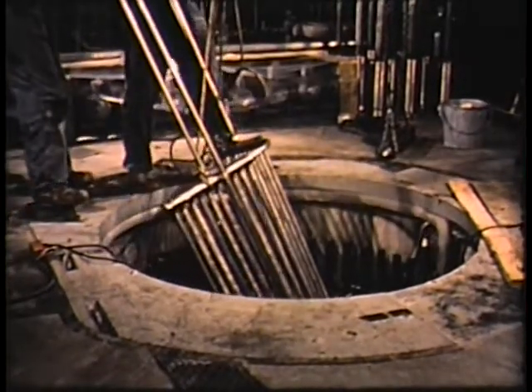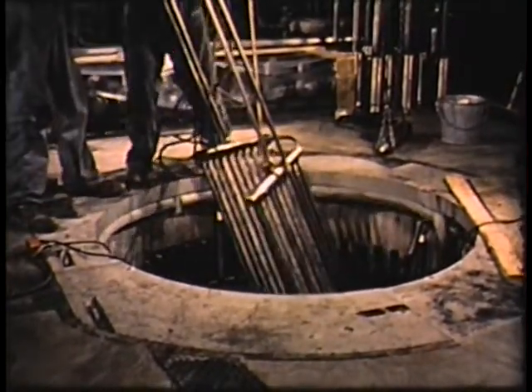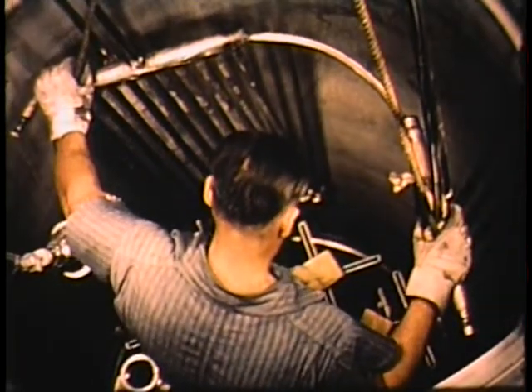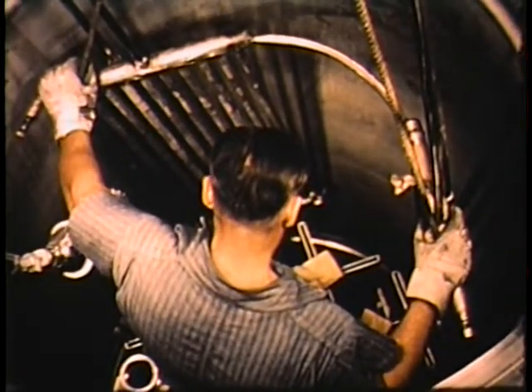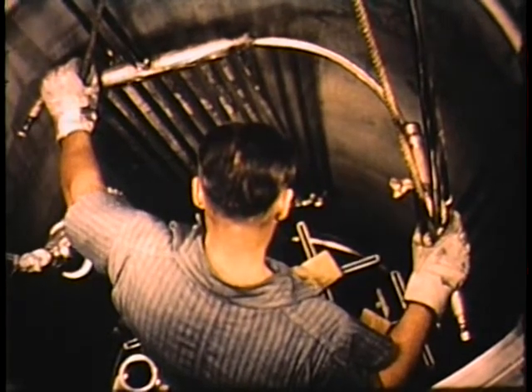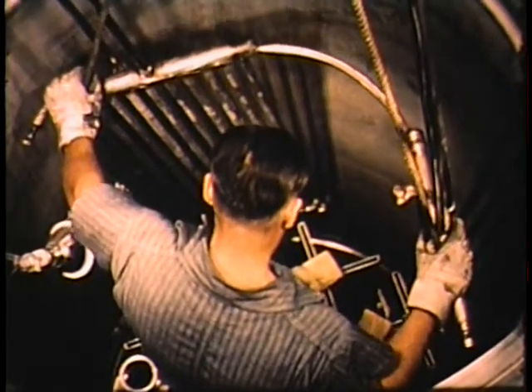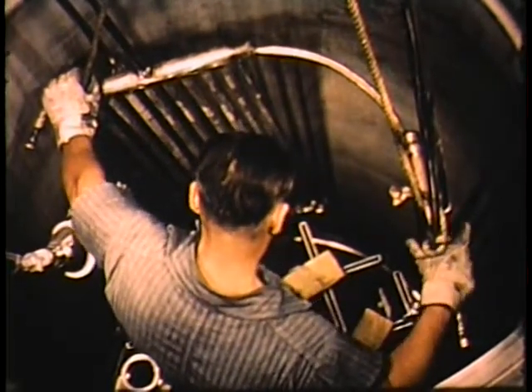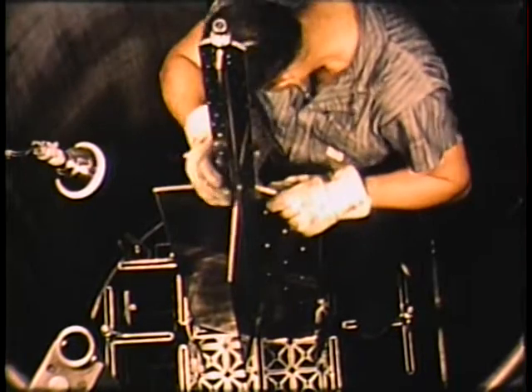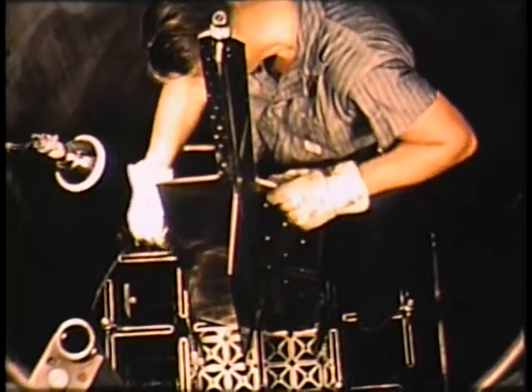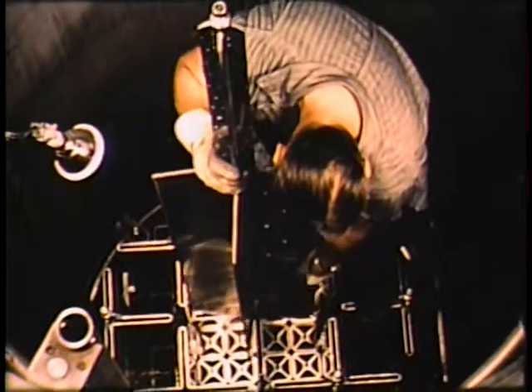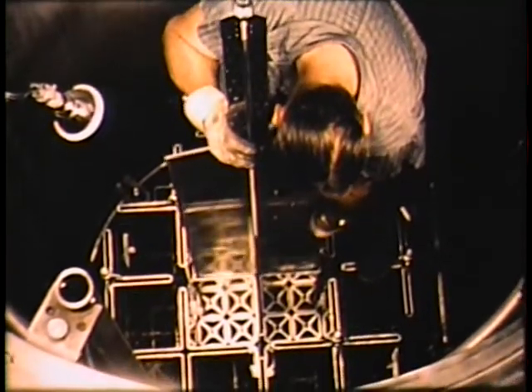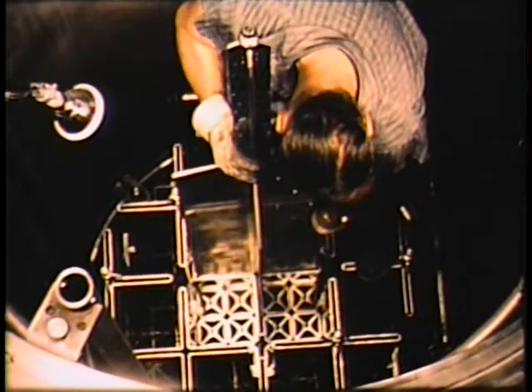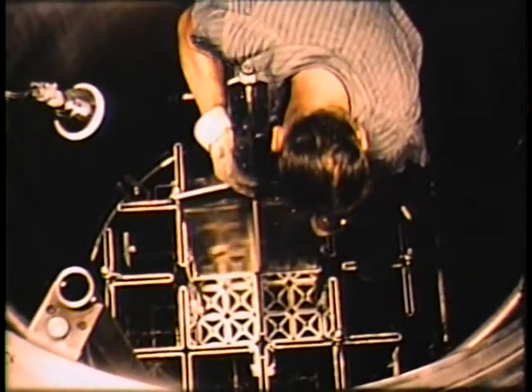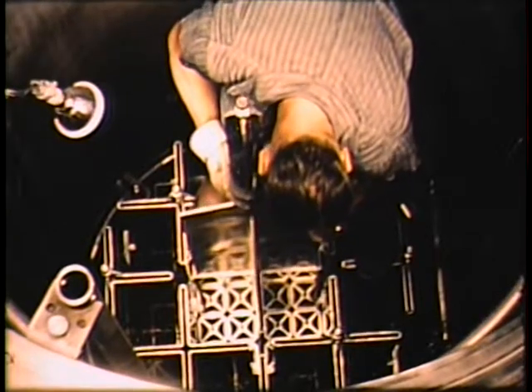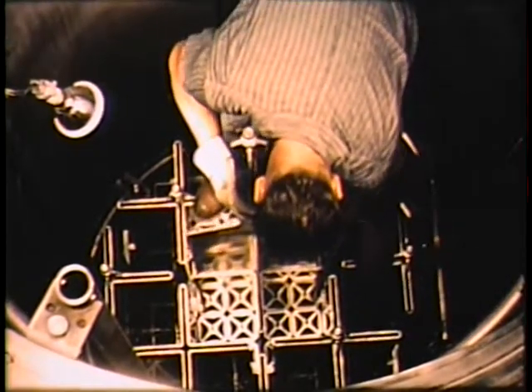Steam heating coils were installed between the core structure and pressure vessel walls. The auxiliary steam heating was used during specific investigations to determine the reactivity effects of operating at various temperatures and pressures without excessively irradiating the fuel assemblies. The control rods were located within the control rod shrouds of the core structure. The neutron-absorbing portion of each control rod is cadmium. The cadmium is enclosed by welded aluminum-nickel plates, protecting it against corrosion and providing mechanical strength.